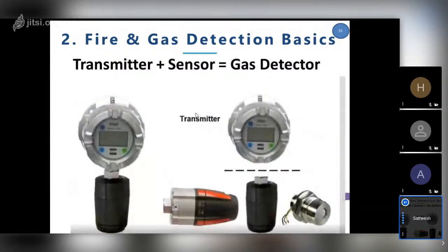You can relate your transducer as transmitter, and the sensor is the actual electrochemical sensor. This is the hydrocarbon or infrared gas sensor, and this is the catalytic bead sensor. So this is electronics, this is a sensor. Together we call it a gas detector: transmitter plus sensor.